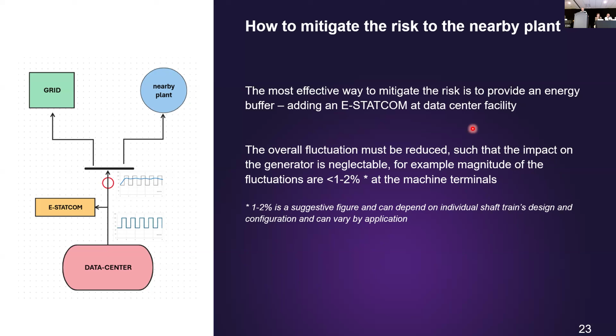Once this is established, we might think about different mitigation measures, which typically lie inside the facility of a data center or at the POI between the data center and the grid. I'm not going to talk about any of the mitigation at the GPU rack level, but from an energy standpoint, the most efficient way to reduce the fluctuation is to add some type of energy buffer between the load and the rest of the grid or the plant. And this is exactly what we are proposing to do with the E-STATCOM.